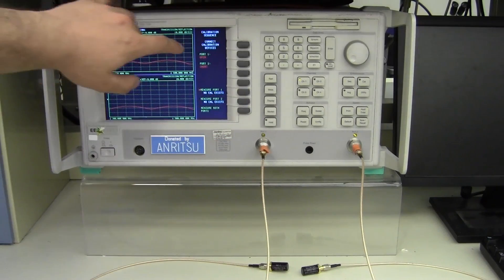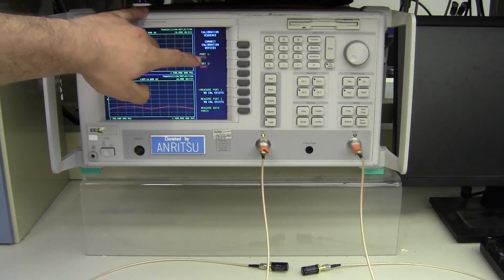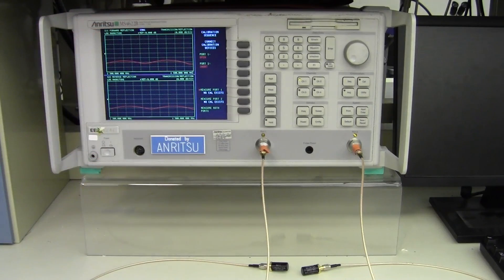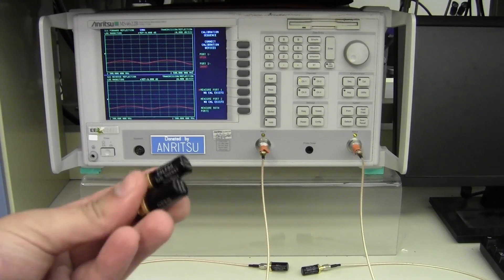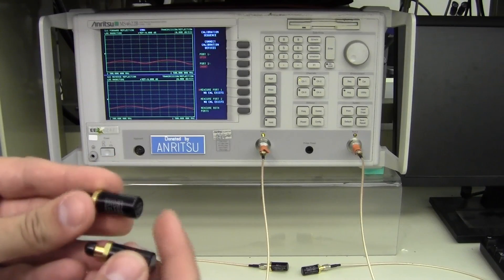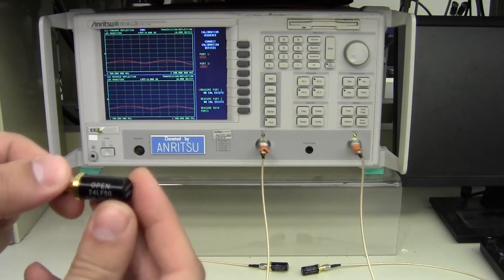For the next calibration step, it specifies that port 1 should have an open load and port 2 should have a short load. Calibration kits, in addition to the two 50 ohm terminations, include two additional loads that are labeled short and open.